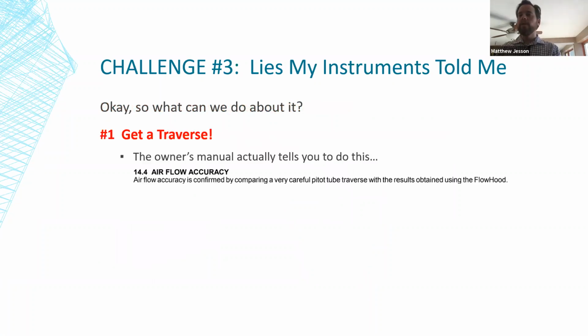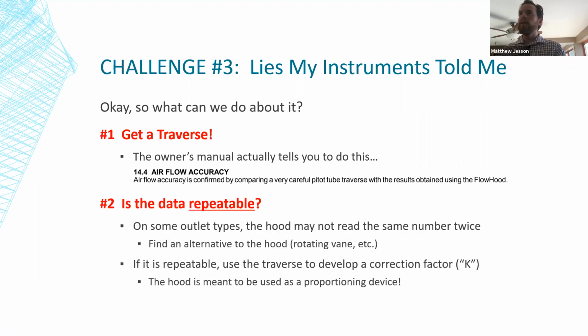The first one is, the same old song, get a duct traverse. In fact, the hood owner's manual actually tells you to do this. It says to confirm your airflow accuracy by performing a pitot tube traverse and comparing that with the results obtained with the flow hood. So it's important to determine, is your data repeatable? Can you get a consistent result? On some outlet types, you might not be able to read that same number twice. And a great example of that is going to be those eyeball diffusers.